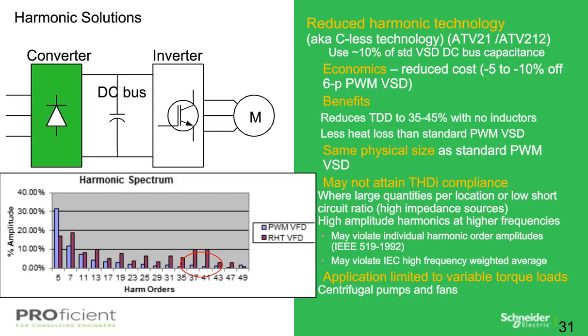Okay. One comment came in, maybe I missed it somewhere, but if the IEEE 519 point of coupling is on the high voltage side of the transformer, why are we required to find solutions for harmonics at a motor level downstream, if there are no real issues? Very good question. IEEE 519 is applicable to both the utility as well as the facility or end user. I can certainly have a more detailed discussion on that, but both stakeholders, the utilities as well as the local facility and end user, are affected.